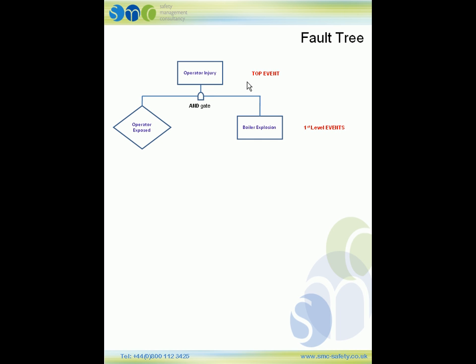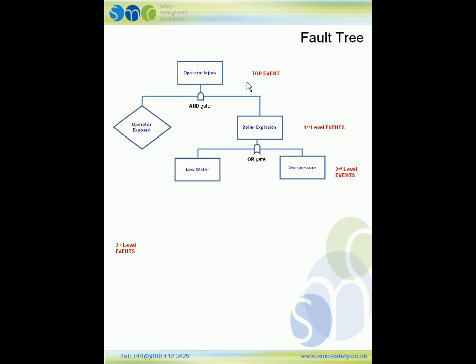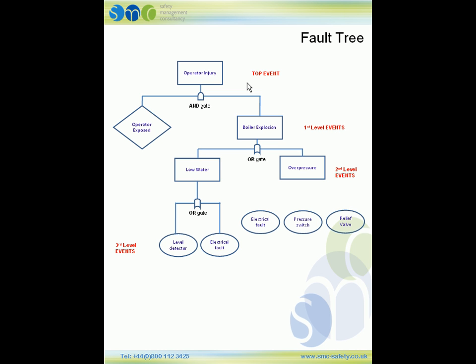Next we look at the events below the boiler explosion, which are the second level events. From the question, the boiler could explode due to either low water condition A or over pressure condition B. Because it could be either of these, we use an OR gate. For condition B, there are three conditions: the electrical fault, the pressure switch, or the relief valve — and again, because it could be any of these, that is also an OR gate.